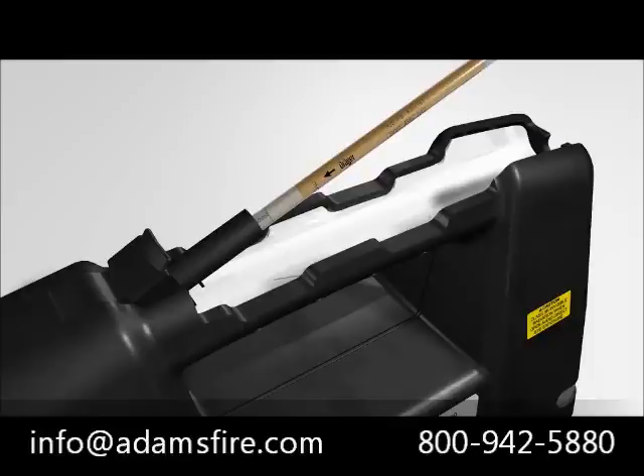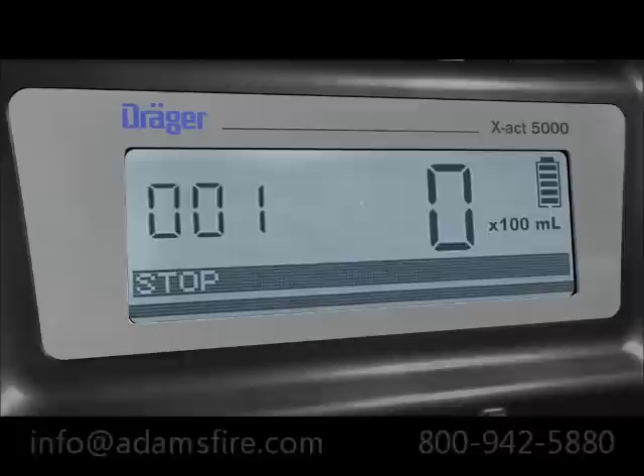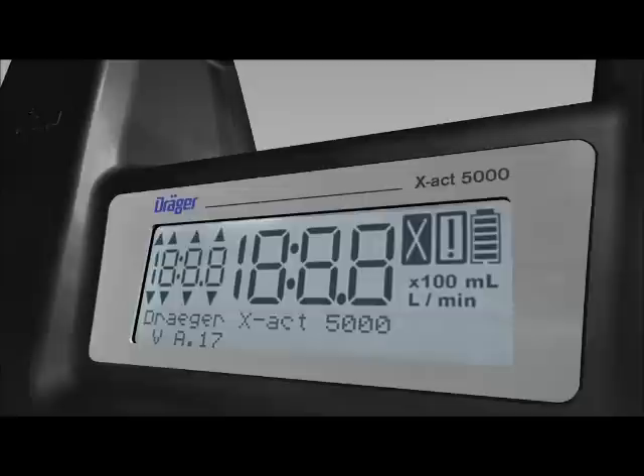After the measuring range has been selected, measurement can start without any additional settings. The display of the Dräger X-act 5000 is extremely bright and can even be clearly read in direct sunlight. It consists of two parts: the upper section is a segment display showing the number of strokes, the flow rate, the measuring time and various icons. The lower section is a matrix display comprising two lines used to show menus and options.